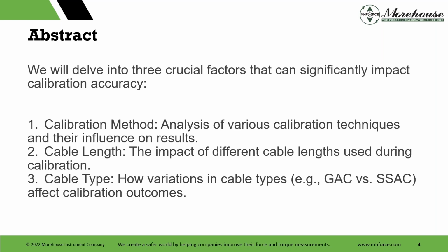Not good. Cable length: the impact of different cable lengths used during calibration. Some systems only use a 2-foot cable. We had a customer ask for an 18-inch cable. We begged and pleaded not to do this, and then they said we need this, and we ended up doing it. And I wish we would have just said no. It's not the right setup. There are some times when it's okay to say no, and that's one I wish we would have said no to. Cable type: galvanized versus stainless steel will affect outcomes.